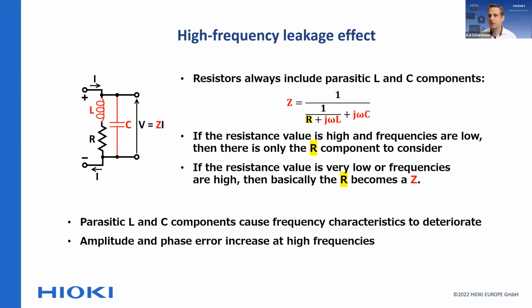And that brings a different negative with it, which is a high frequency leakage effect. Effectively, every resistor has inductive and capacitive components. You just don't notice them if you have higher resistance values, but the lower the resistance value becomes and the higher the frequencies you're working with, the more important the L and C values become, the inductance and the capacitance. And in this case, you can see that there is an amplitude and a phase error that increases massively in the shunt. That's actually the reason why shunts can be used either for high currents or for high frequencies, but typically not at the same time. So that is the downside with shunts.